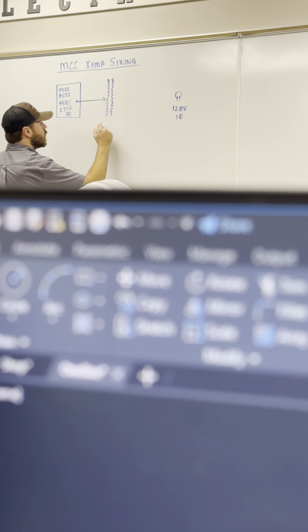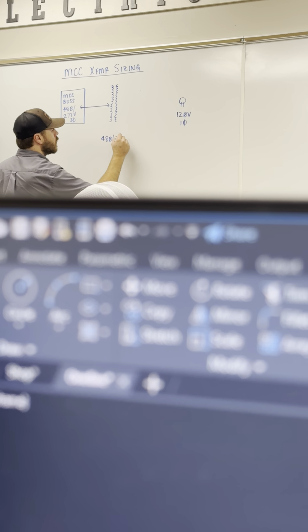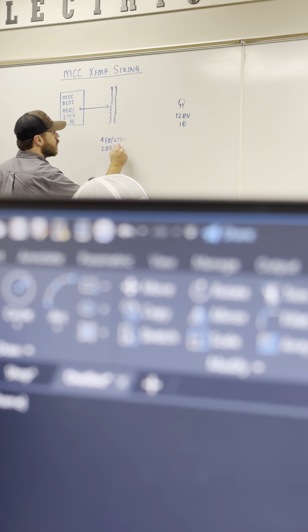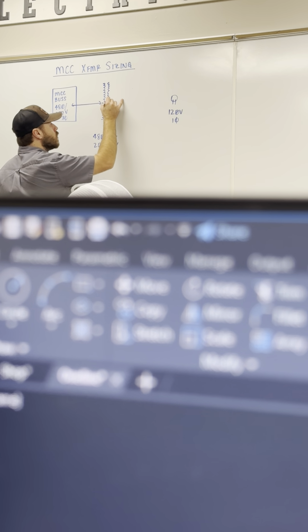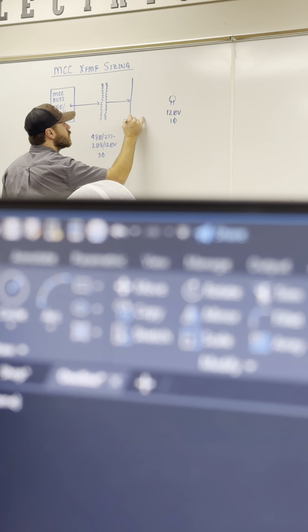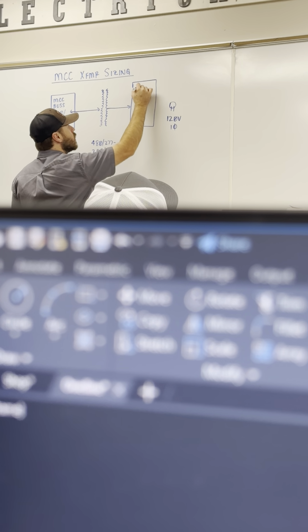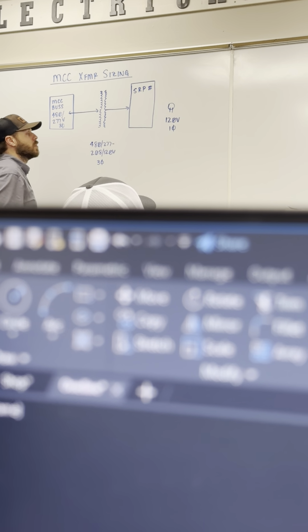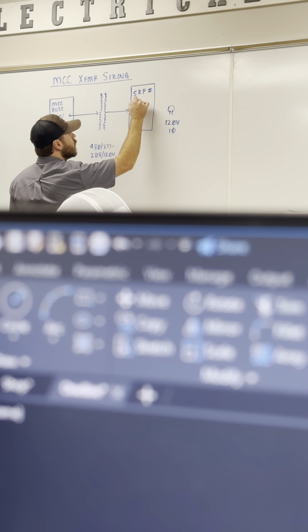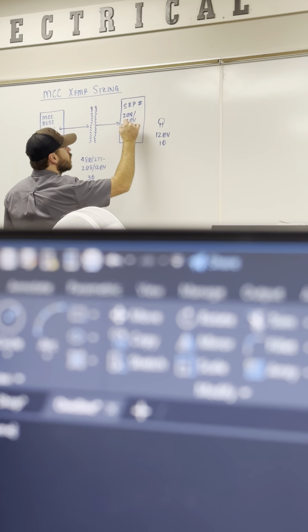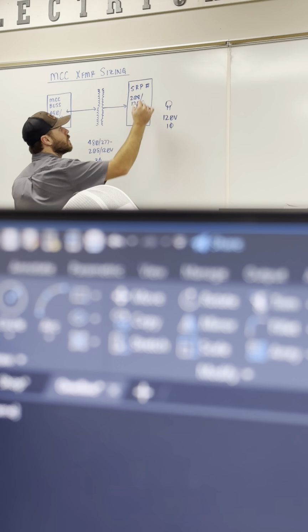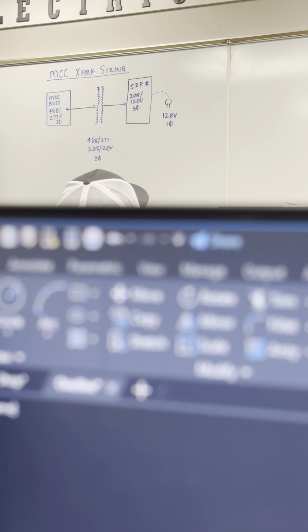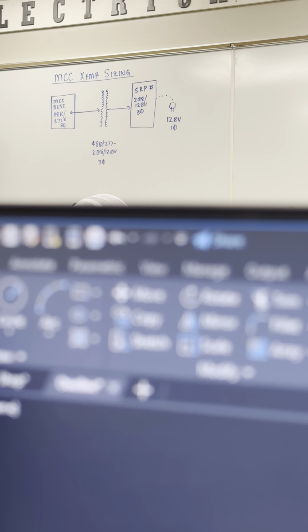So we're going to size a transformer that goes from 480, 277 down to 208, 120. You might ask, well, why that? Well, because this transformer is then going to feed what we're also going to install today, but that is a panel, and we're going to call that shop receptacle panel, number whatever. Each MCC is going to have one. And of course, this is going to have our 208, 120 available in here, and also be a 3-phase panel. But we could just take a single phase of that and run out to our receptacles. Like I said, this is going to be in every single MCC. This is the exact same process. So this is going on inside of section 6 there.